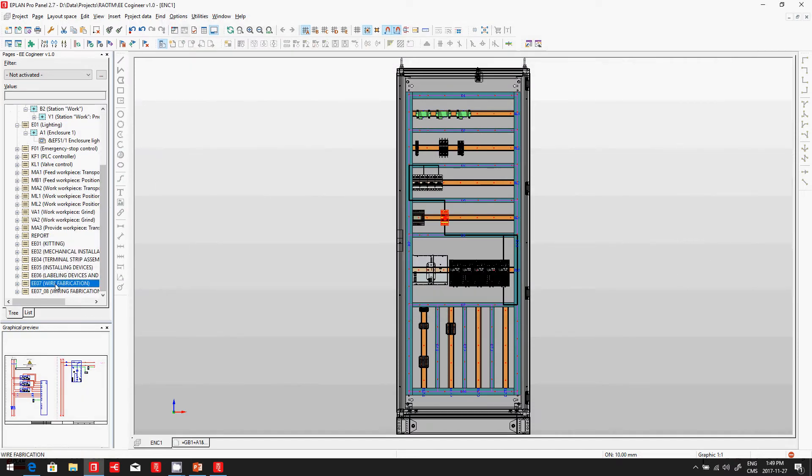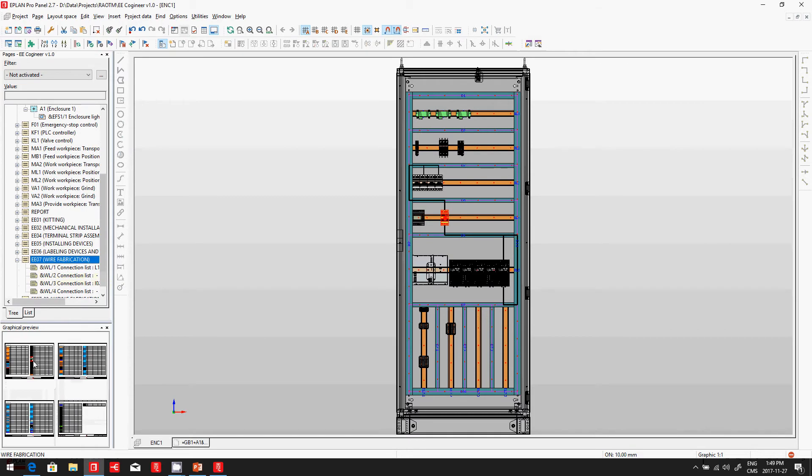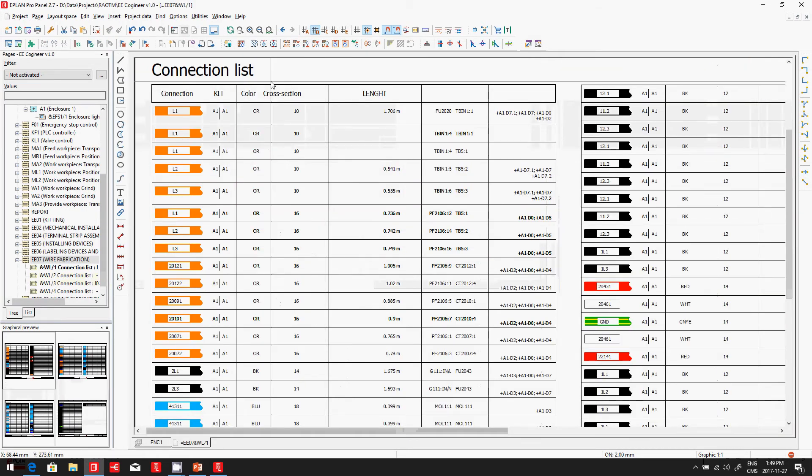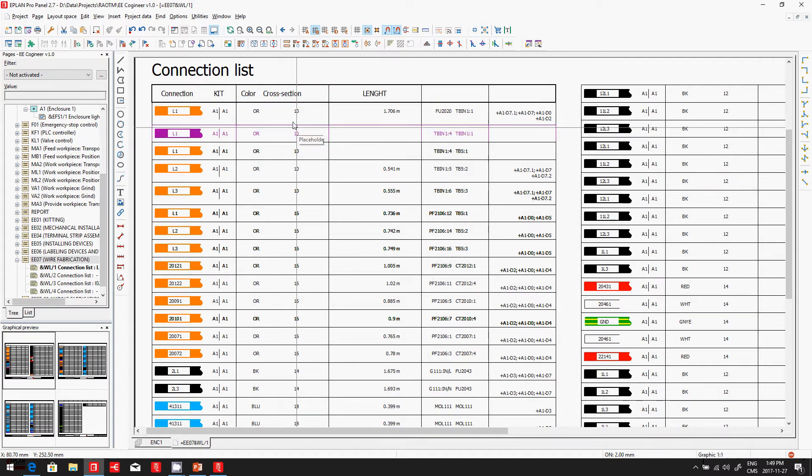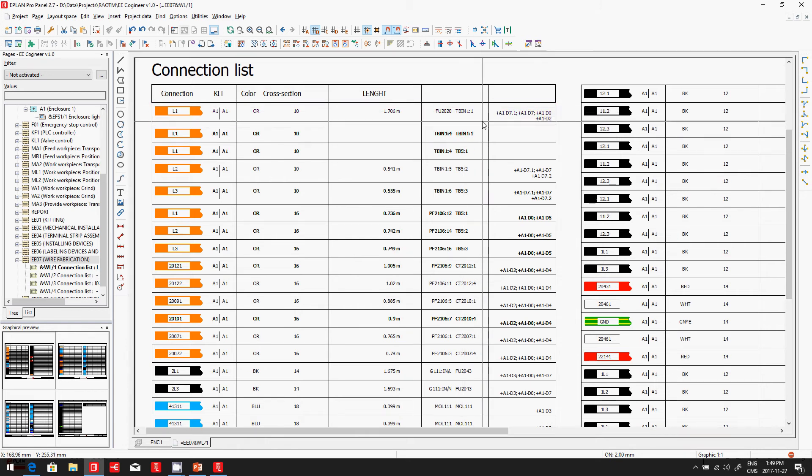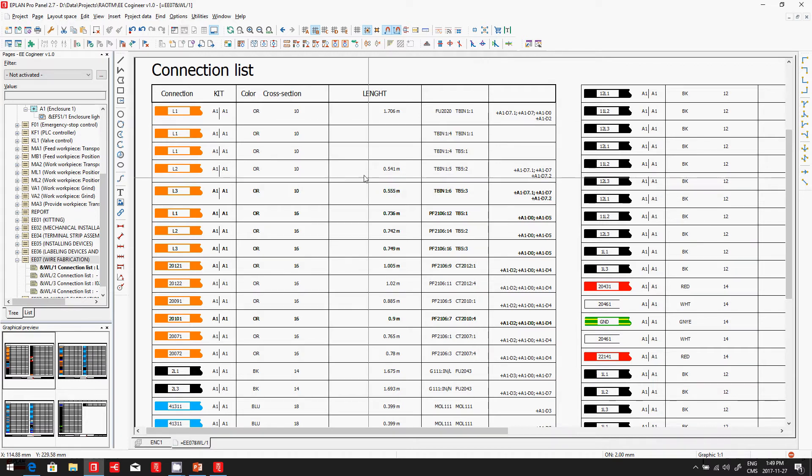First, how can we help the electrician build his wire? Here is a connection list with the different wires. We show you in which kit it goes. Here I'm actually putting together the A1 to A1 kit, which is everything that's inside my panel A1. I have an orange wire, gauge 10, and a certain length. It even tells you from where to where it goes, from what device to what device. And I'll have this prefabricated if it's possible, because I have the exact length.